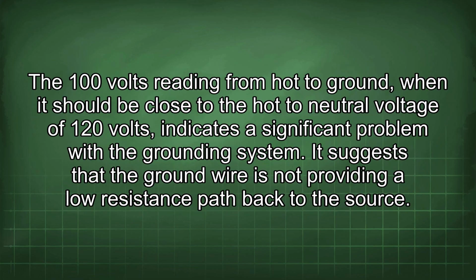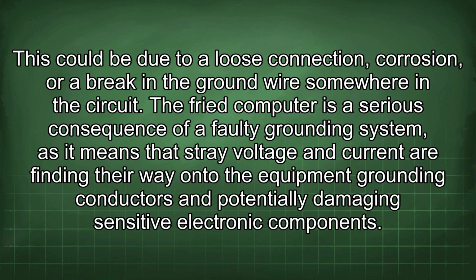The 100 volts reading from hot to ground, when it should be close to the hot to neutral voltage of 120 volts, indicates a significant problem with the grounding system. It suggests that the ground wire is not providing a low resistance path back to the source. This could be due to a loose connection, corrosion, or a break in the ground wire somewhere in the circuit.